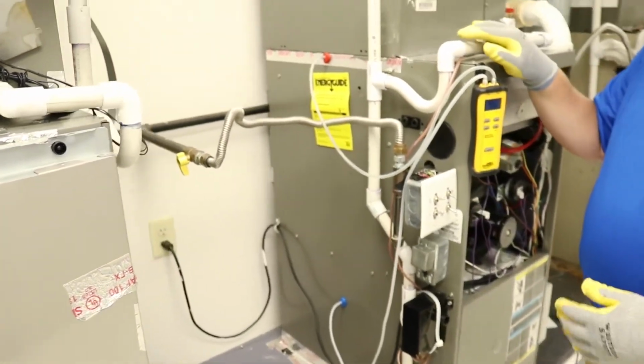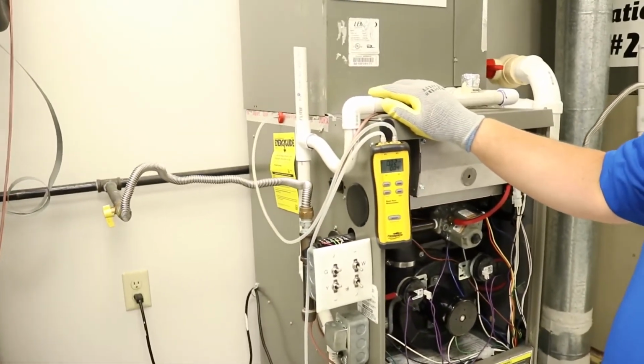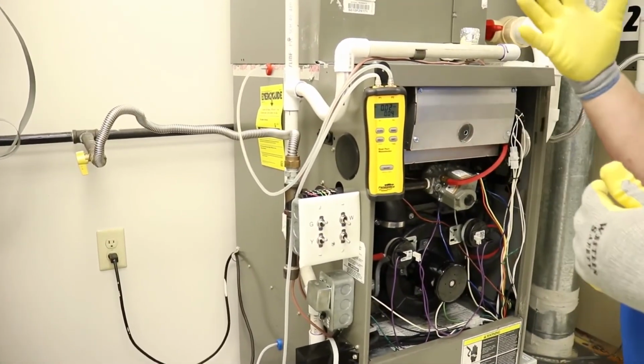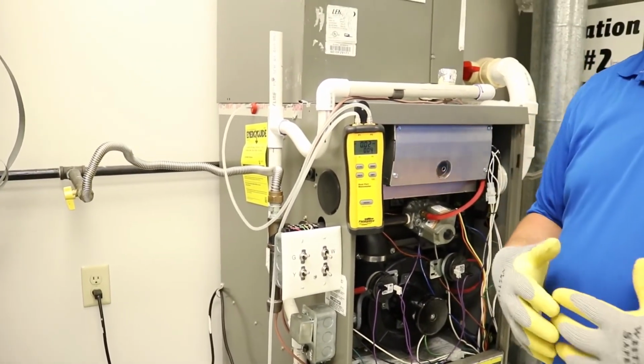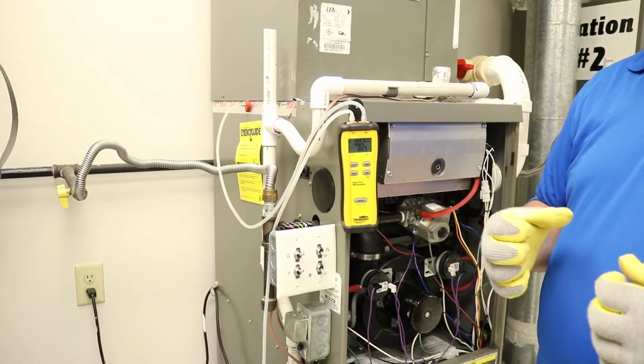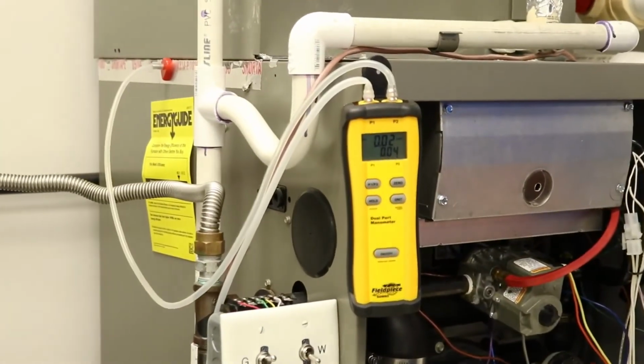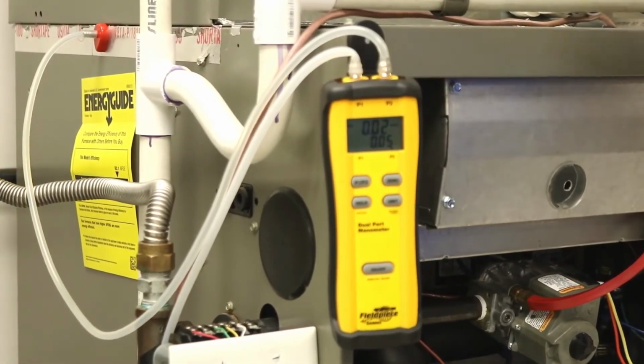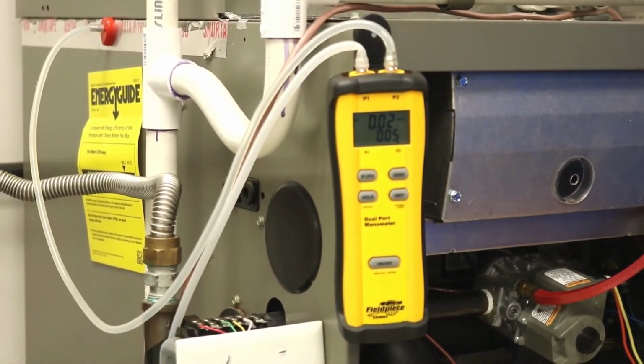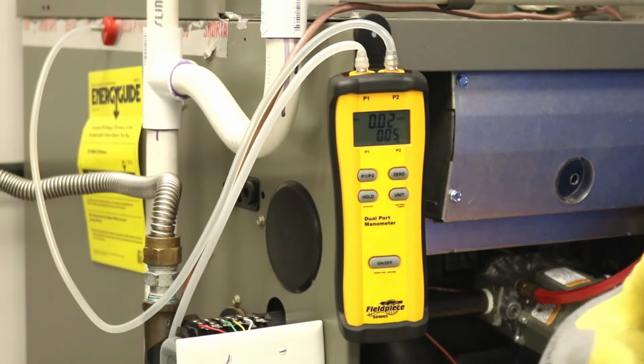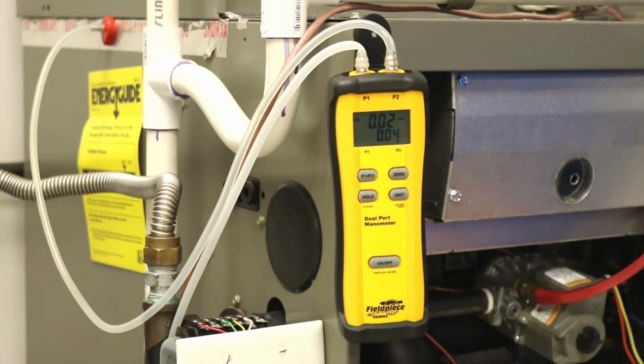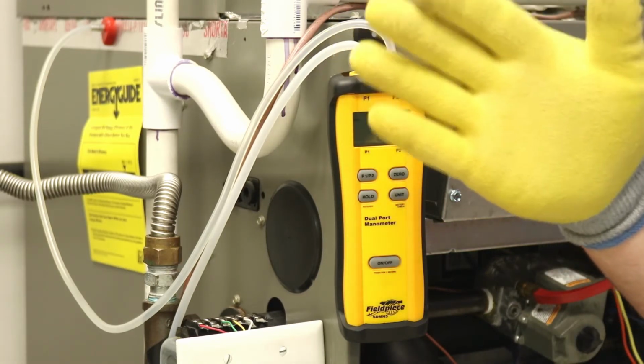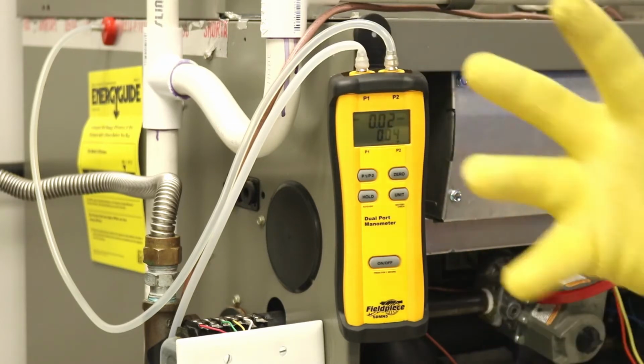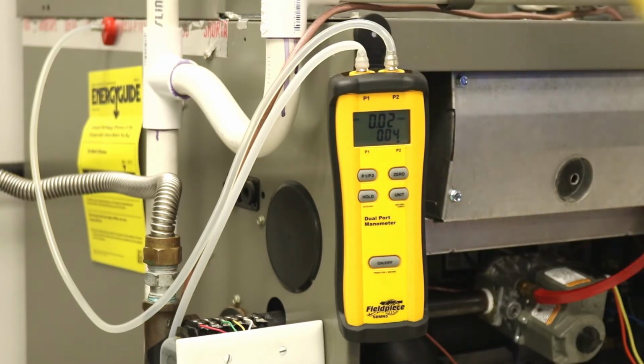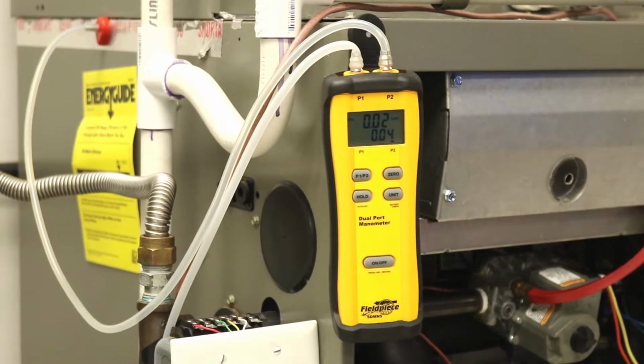The reason that that is so important is because the evaporator coil and the filter are going to affect that static pressure. And if you're on the other side of it, you're not getting a proper reading. So let's make sure that, like I said, you keep it inside the box. Now for an air handler, your evaporator coil is a part of that box, so it's important to make sure that it's before the filter, and then after or by that blower motor. So making sure again that it stays inside that box. Don't go outside of that furnace cavity. Don't go outside of that air handler cavity.